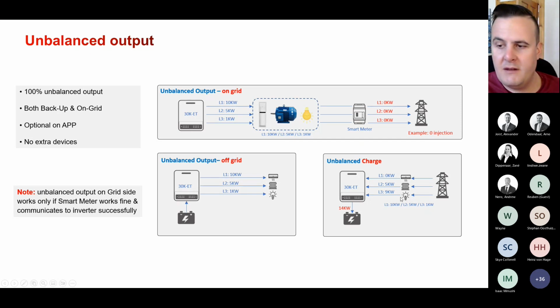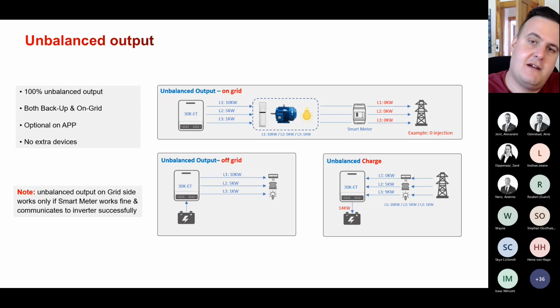We'll see that. And then we can also do unbalanced charging. If we charge the batteries from the utility, if we're using it just as a UPS or a time-of-use tariff kind of device, it will unbalance charge. It will draw unbalanced power from the phases to make the consumption from the utility equal. This is especially valuable for any kVAR-billed customers. It doesn't just pull everything per phase and increase that kVAR consumption from the grid. It will draw from the phases that are using the lowest amount of power and then use that AC power to charge the batteries.